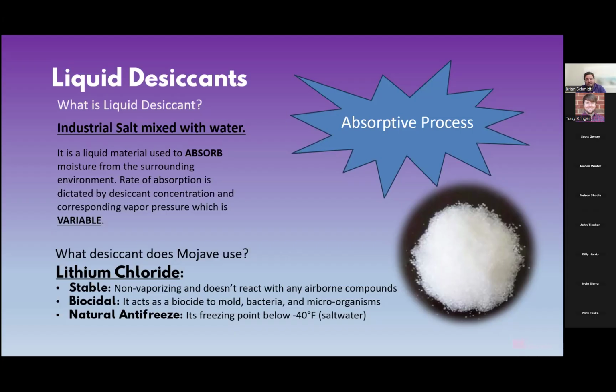So what desiccant do we use? There are multiple desiccants that can be used. We use lithium chloride. There's also lithium bromide. There's several hybrids as well. The reason that we chose lithium chloride, a couple of reasons. One, it's stable, so it's non-vaporizing. It doesn't react with any airborne compounds. The only compound I know that it does interact with is hydrochloric acid. So unless that is in the airstream, you don't have anything to worry about. It is also biocidal. So it acts as a biocide to mold, bacteria, and microorganisms.